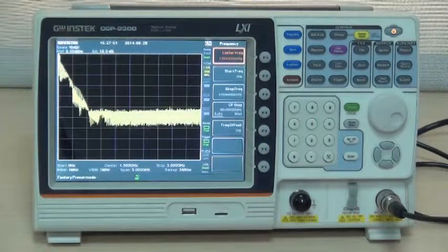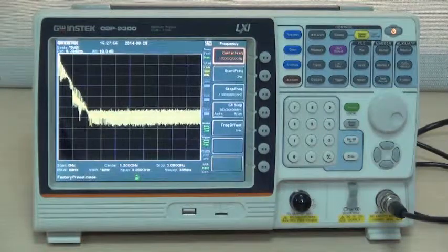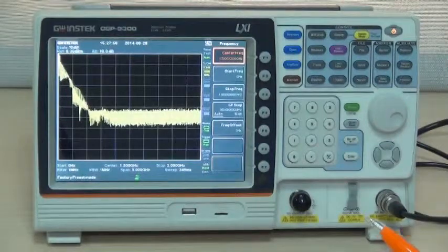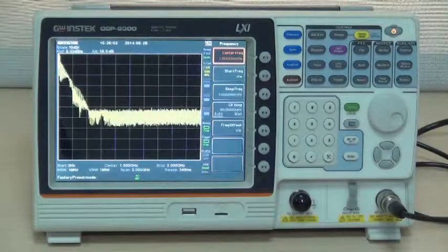First, connect the 10 MHz reference signal output terminal from the GSP9300 rear panel and the GSP9300 input terminal with a BNC cable.